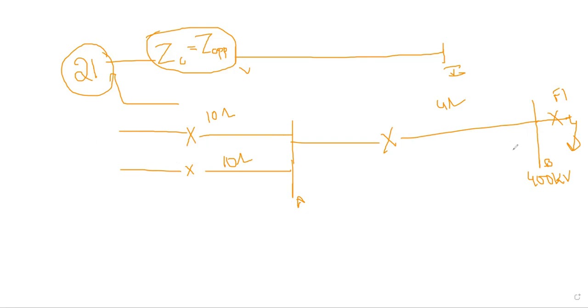First case, if I am using overcurrent protection here, then let's see. If a fault is coming in this direction and occurred here, it should operate in 200 milliseconds. Then this should operate in 400, then 600. So what is the issue? In India, the entire grid is a very meshed network, so we cannot grade based on normal overcurrent protection. This is the way our general overcurrent protection works.